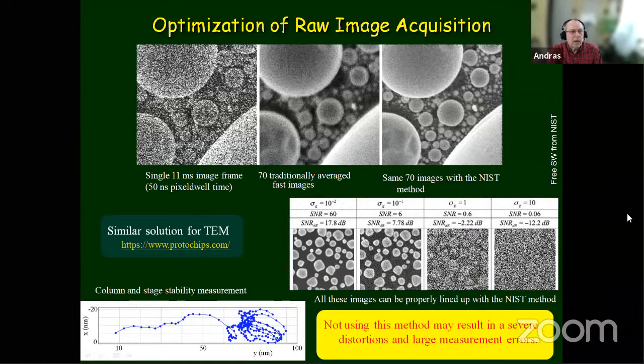A similar solution for the TEM is available, even as an aftermarket solution from Protochips. They showed very nice images when you do heating in your TEM or STEM, and then instead of waiting for a long time or doing all kinds of tricks, the software solution keeps everything stable and in focus. You can see at the bottom that we plotted what the stage was doing over time. You can do that, and it also allows you to check whether the stage performance is all right.